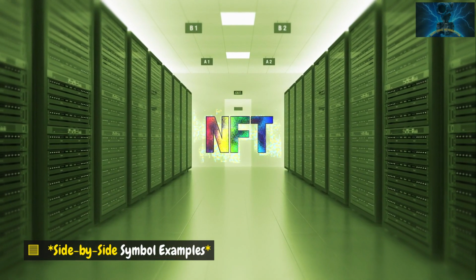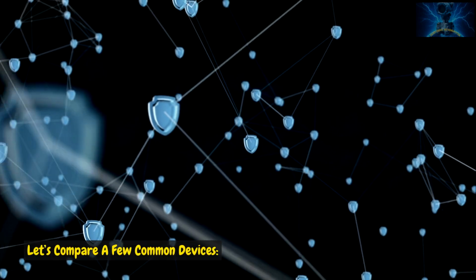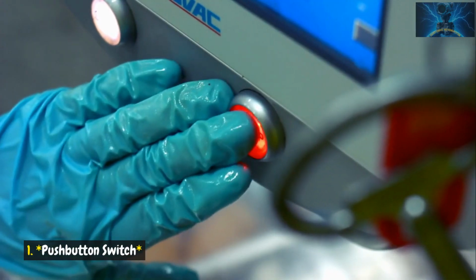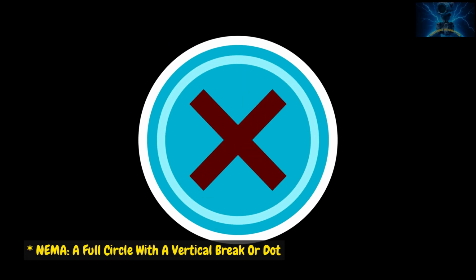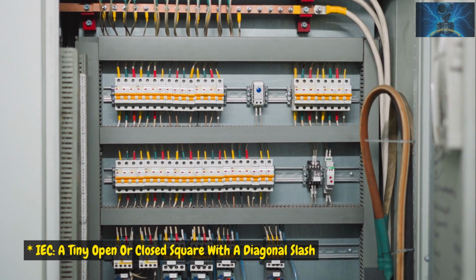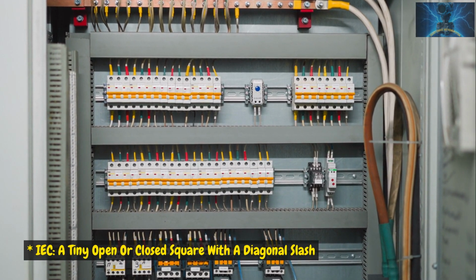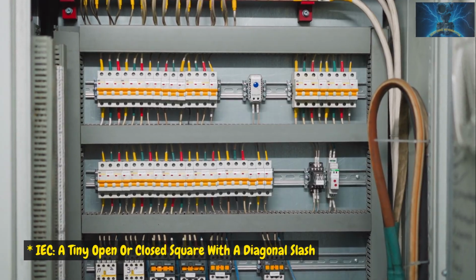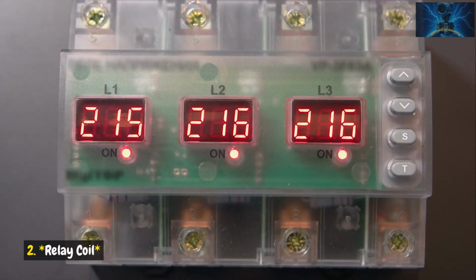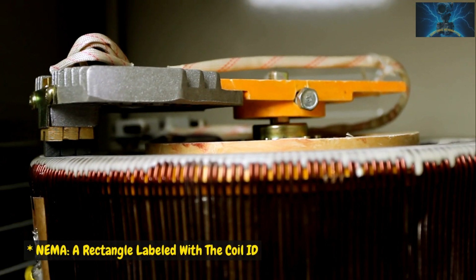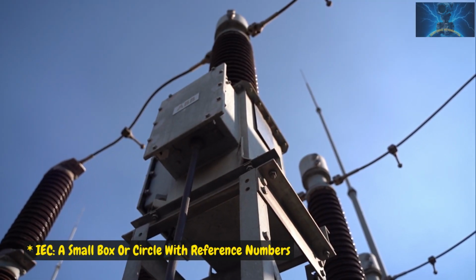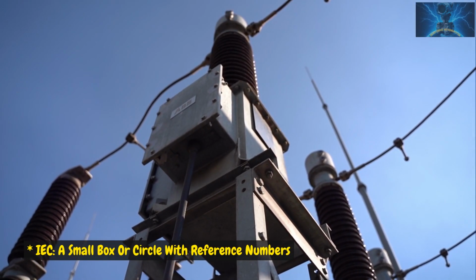Side-by-side symbol examples. Let's compare a few common devices. 1. Push-button switch. NEMA: a full circle with a vertical break or dot. IEC: a tiny open or closed square with a diagonal slash. 2. Relay coil. NEMA: a rectangle labeled with the coil ID. IEC: a small box or circle with reference numbers.